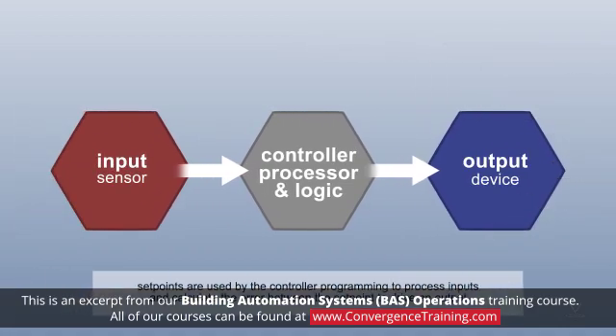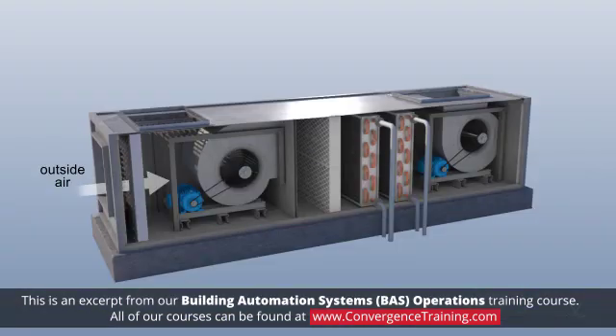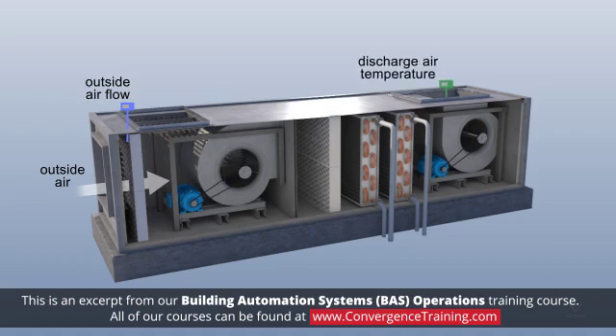Set points are used by the controller programming to process inputs and calculate the error between the set point to drive an output. Some types of set points or critical sensors on a typical air handler include outside air flow, discharge air temperature, and duct static pressure.